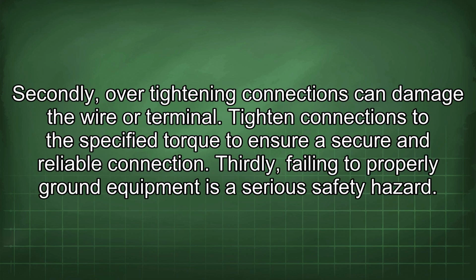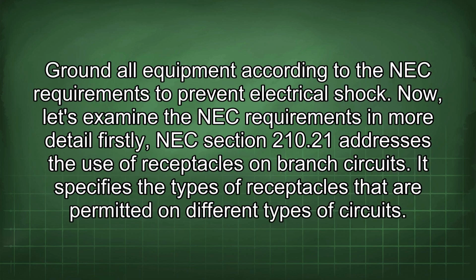Secondly, over-tightening connections can damage the wire or terminal. Tighten connections to the specified torque to ensure a secure and reliable connection. Thirdly, failing to properly ground equipment is a serious safety hazard. Ground all equipment according to the NEC requirements to prevent electrical shock.